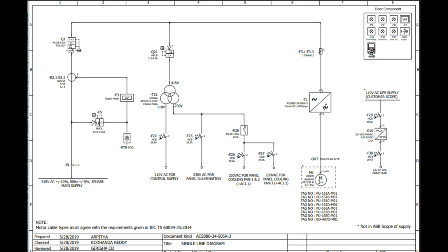Again we have to go ahead and see another tapping, that is for Q21 MPCB, and the rating here is also less, 0.25 to 4 amps, and this is for the control transformer. Here you can see the symbol of the control transformer. Main supply is 415 volt and we will take two phase here. This is a single line diagram, it is not quite clear, but we will take two phase here for 415.